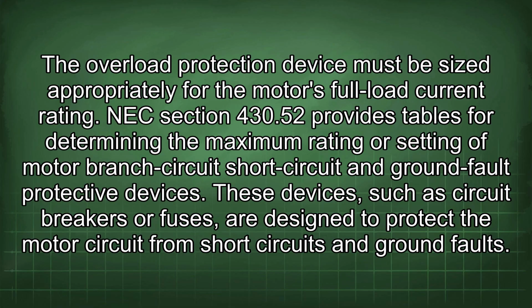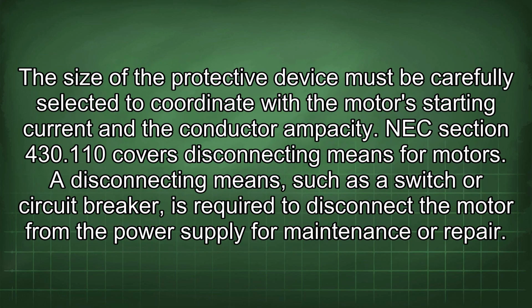NEC Section 430.52 provides tables for determining the maximum rating or setting of motor branch circuit, short circuit, and ground fault protective devices. These devices, such as circuit breakers or fuses, are designed to protect the motor circuit from short circuits and ground faults. The size of the protective device must be carefully selected to coordinate with the motor's starting current and the conductor ampacity.